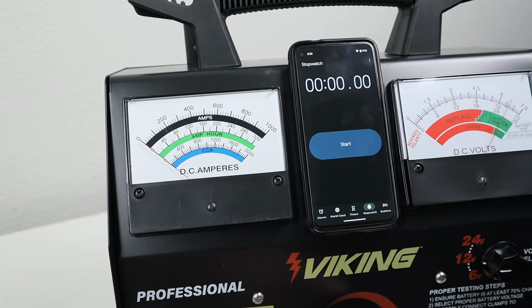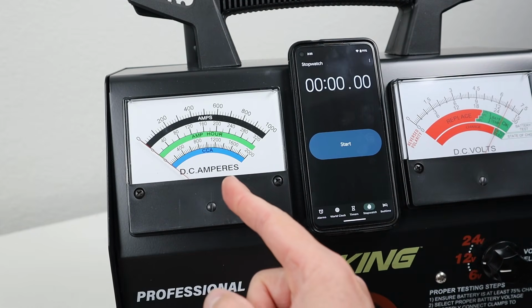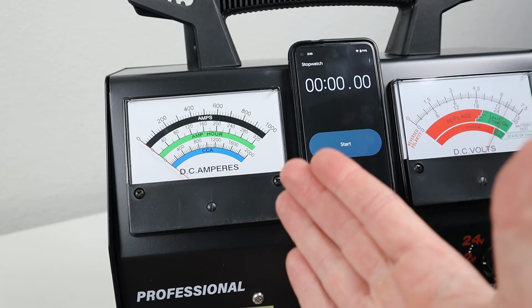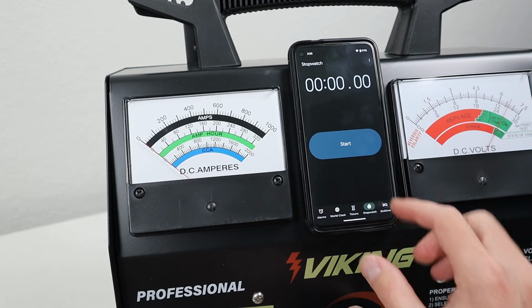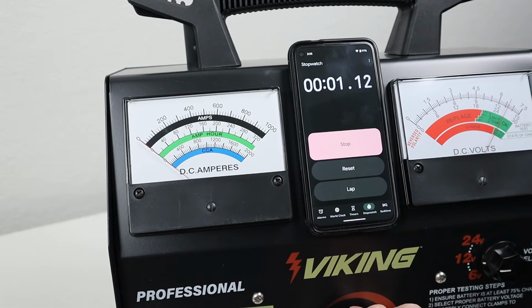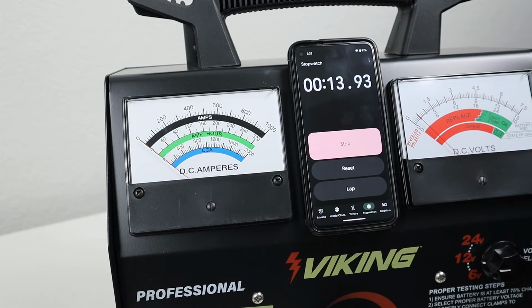In the next test, I want to see what happens as I slowly ramp up the amperage — what level is the BMS going to shut off at. Let's start this and turn it up: 100, 200, 300, 400, 500, 600. Right around the 600 amp level, the BMS shut off.